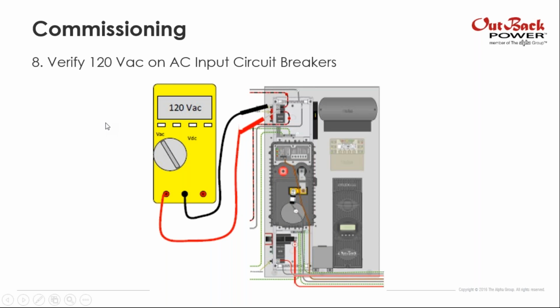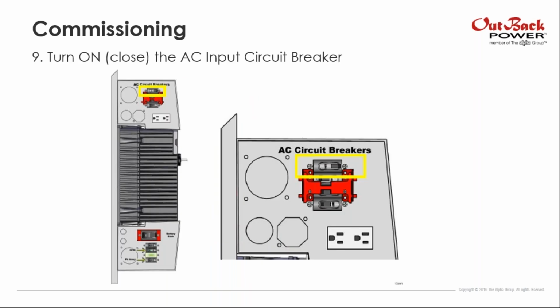Then you have to verify that you have 120 on the input circuit breakers. If you have a generator running or you are using the grid in this breaker, you will have to check that you have that voltage. Then if you are going to use your input, you just need to turn on the AC input breaker and then you have it.